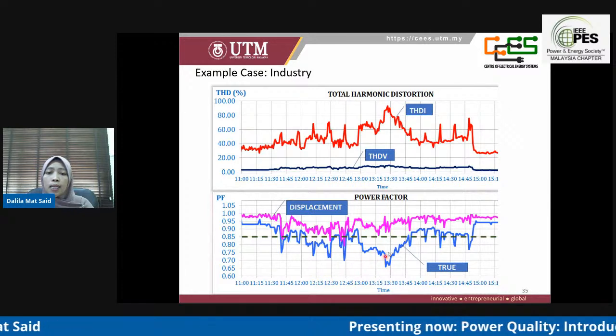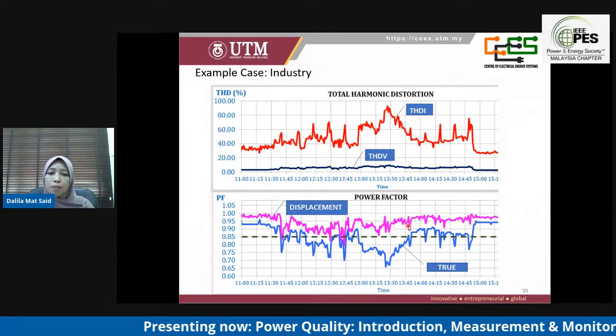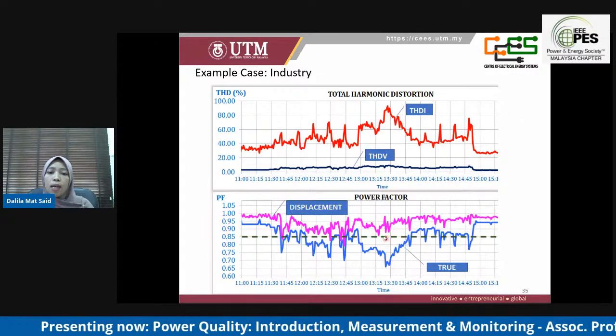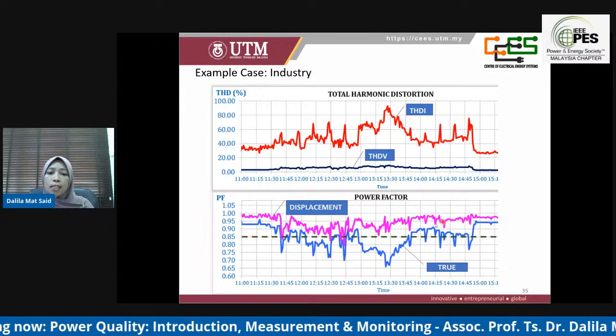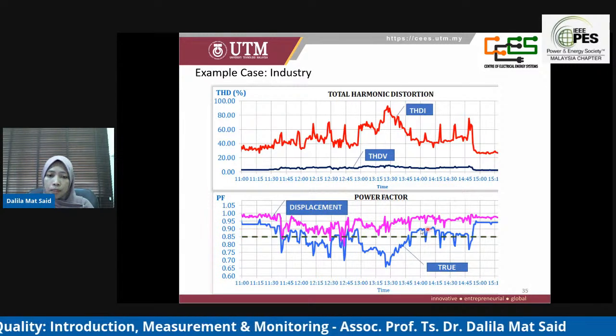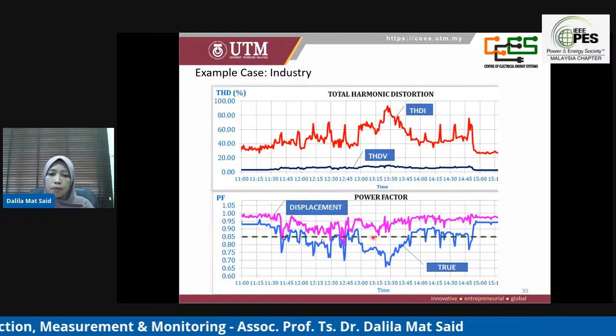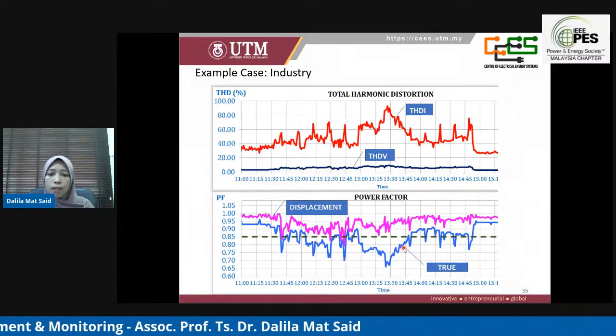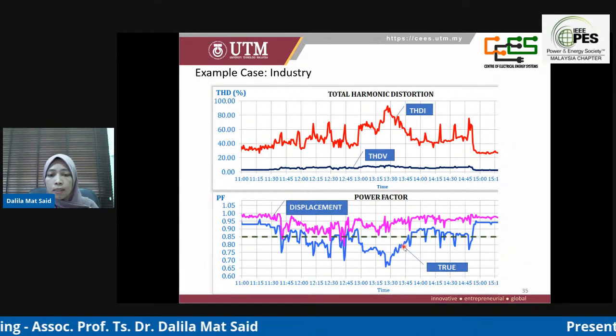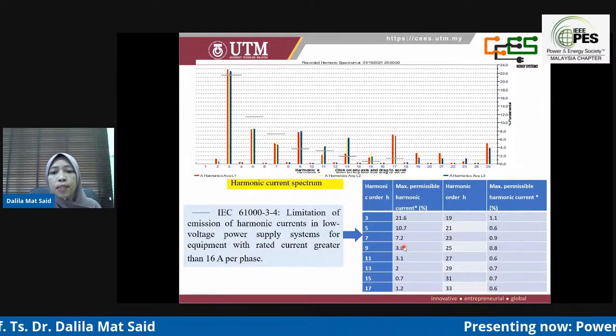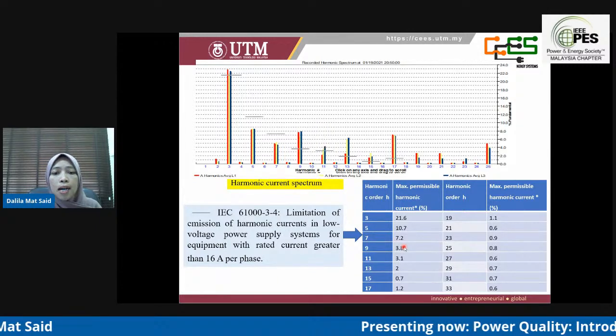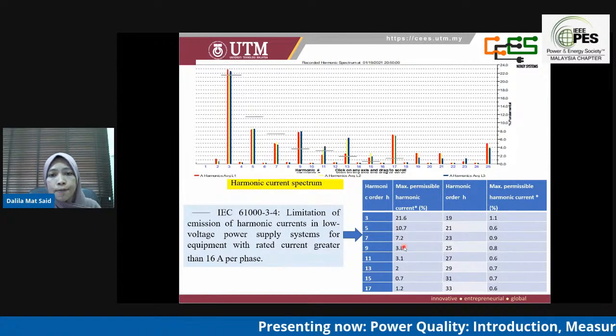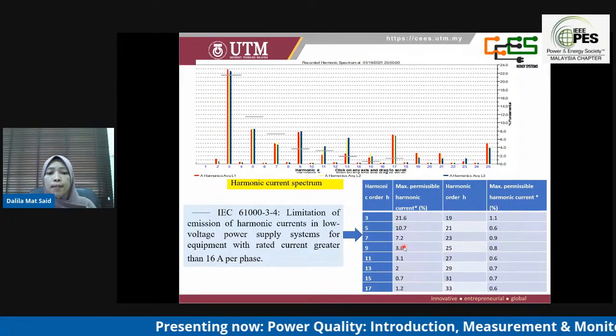The blue color indicates the true power factor, and the purple color gives the displacement. We can see the different values. And the line here is the limit set by TNB, which is 0.85. So next we go to the analysis, the next analysis in harmonics.